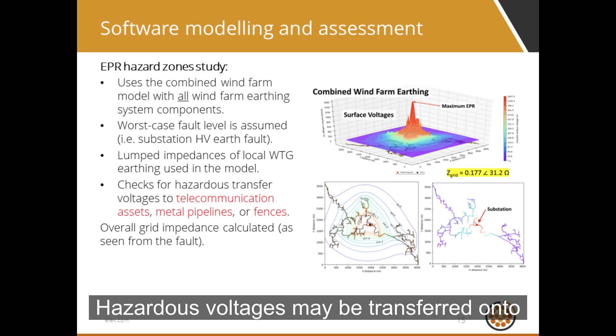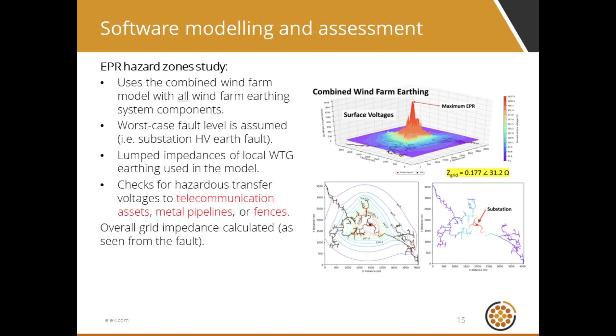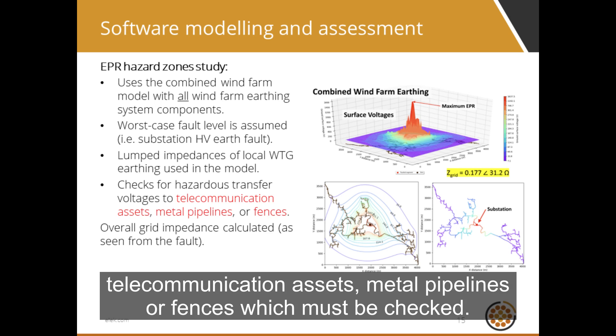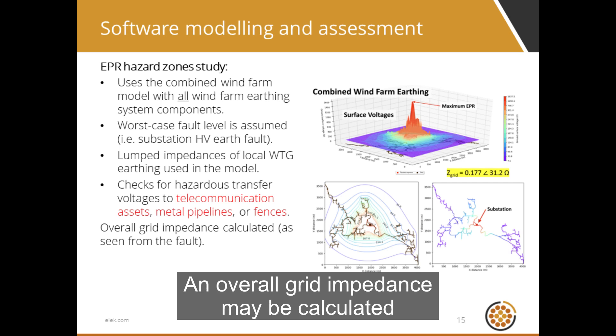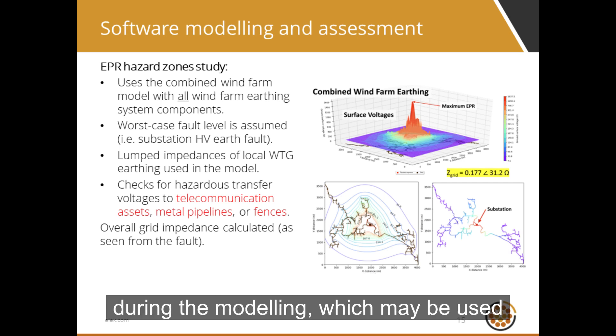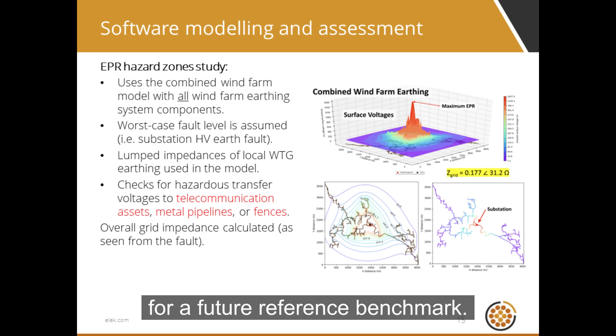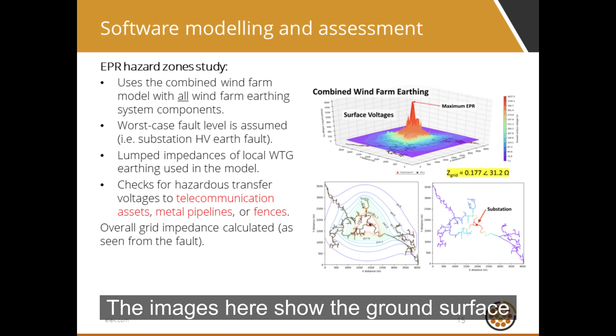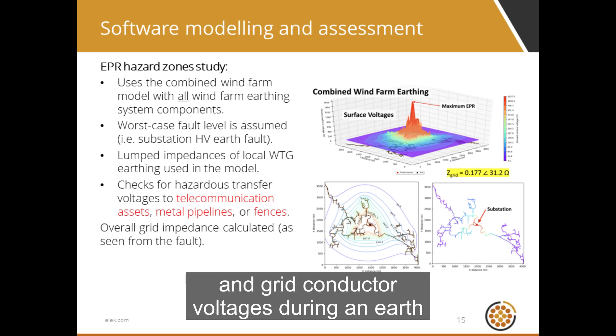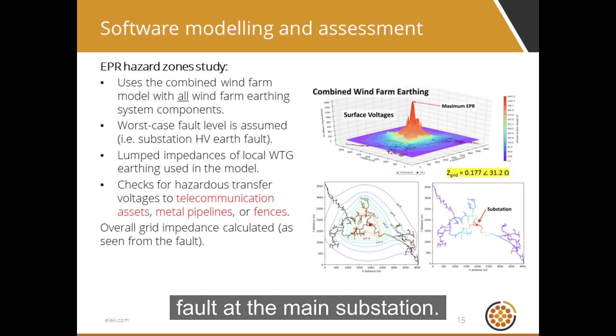Hazardous voltages may be transferred onto telecommunication assets, metal pipelines, or fences, which must be checked. An overall grid impedance may be calculated during the modeling, which may be used as a future reference benchmark. The images here show the ground surface and grid conductor voltages during an earth fault at the main substation.